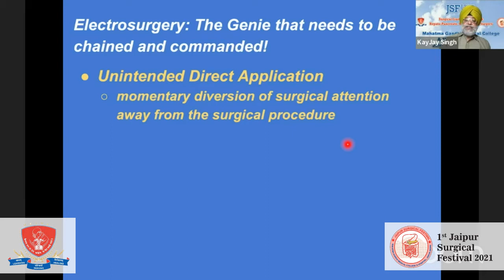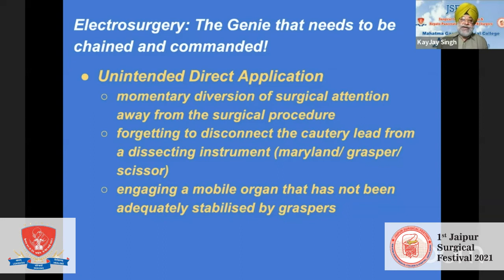So suppose the surgeon is taking a call and he's also handling the cautery. It can be an unintended direct application. Forgetting to disconnect the cautery lead from a dissecting instrument, that will be a Maryland grasper or scissor. If you for a moment wanted to coagulate with a grasper but forgot to take off the lead, and then somebody accidentally presses the pedal, you had it. Engaging a mobile organ that has not been adequately stabilized with graspers can slip during the application of current, and then can create a problem of unintended site coagulation or cutting.